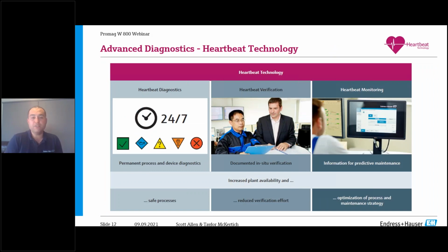The next part is about verification. If you're not familiar with Endress+Hauser and our philosophy around diagnostics and verification, we refer to this as heartbeat technology. Under this concept we have three pillars: diagnostics, verification, and monitoring. Diagnostics is about meter health and status, with the meter continually checking its own diagnostics. We have a symbol system here under NAMUR, the NE 107 standard, which is the international standard for instrument diagnostics.